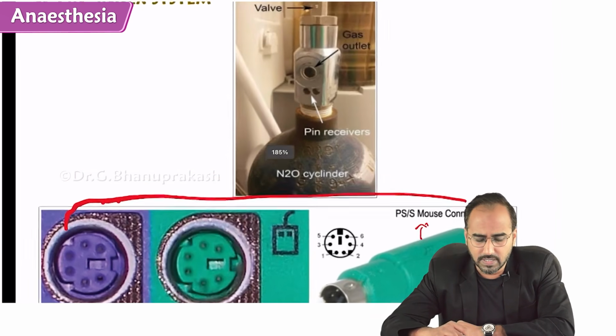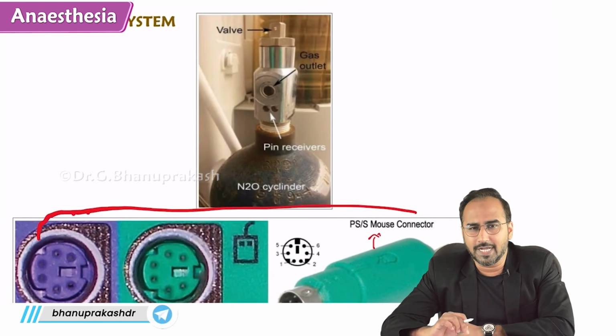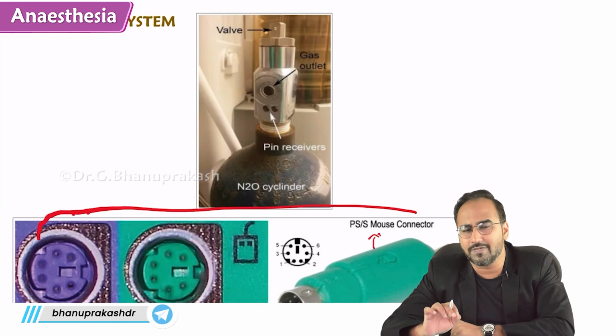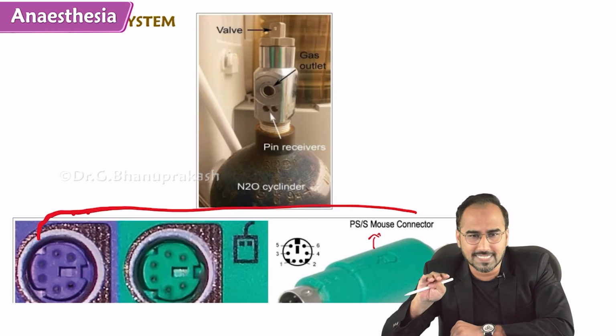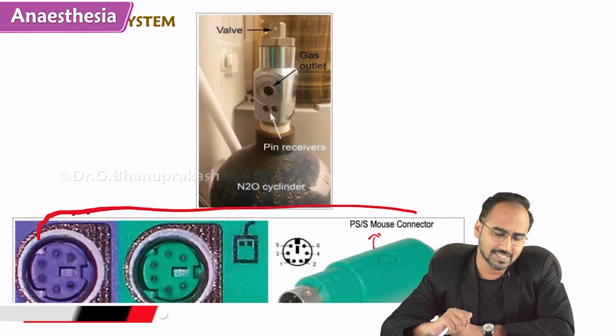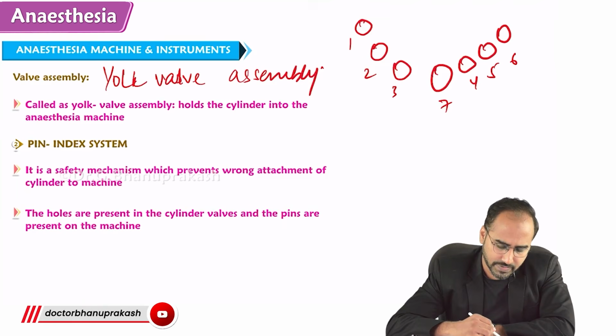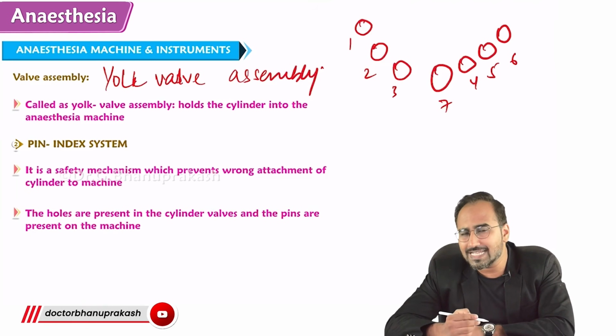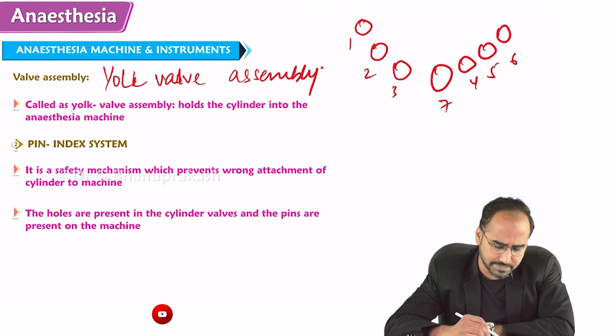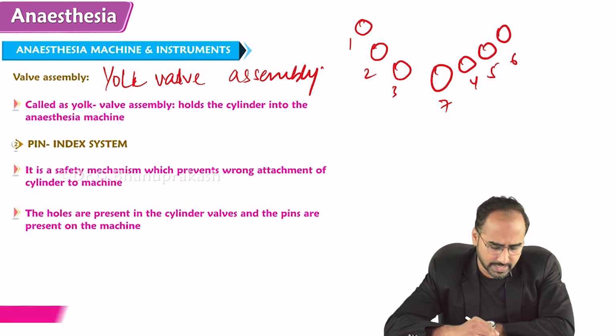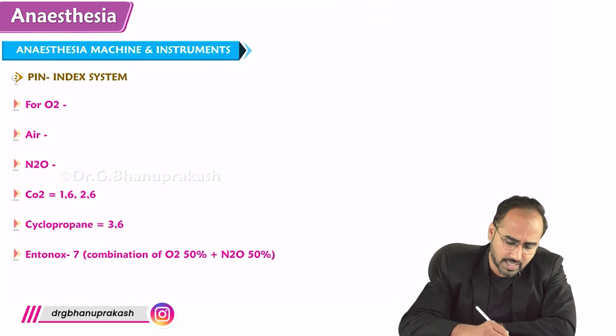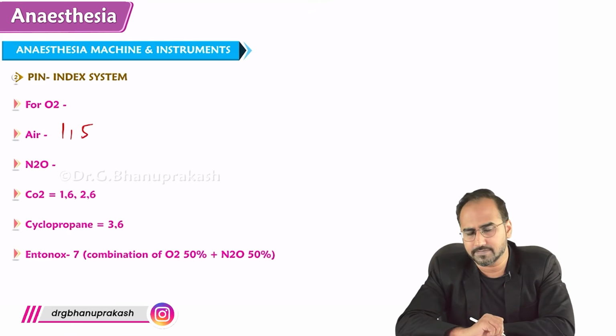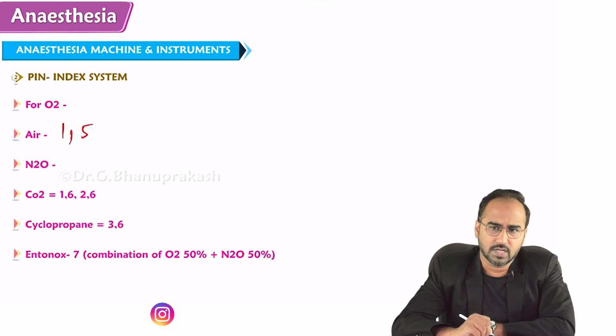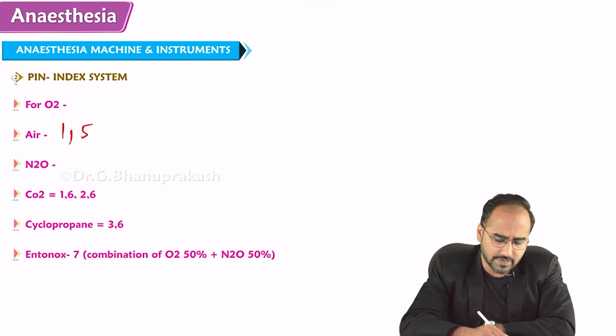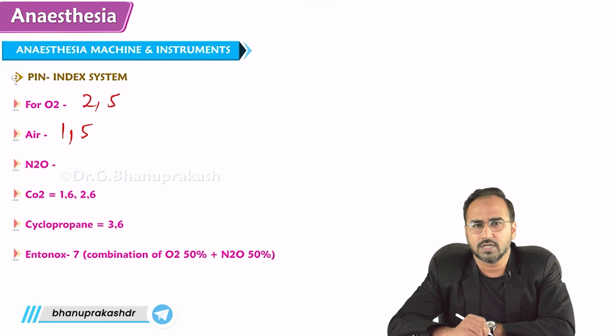So remember, guys, we are discussing the pin index system. The function of the pin index system is to prevent the wrong attachment of the cylinders, where the pins are present on the machine and holes are present on the cylinder. Different gases are given different pin index positions to prevent wrong attachment of the cylinder. Just look over here, guys. What is the pin index for air? Air has a pin index of 1, 5. Oxygen, what is the pin index? The pin index for oxygen is 2, 5.